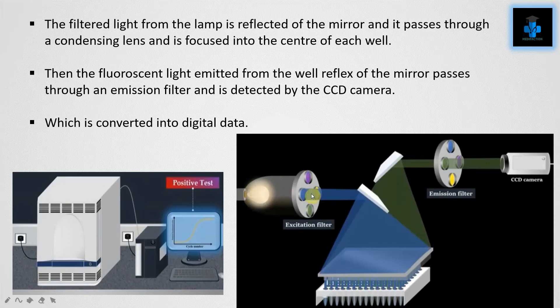A charge-coupled device, or CCD camera, is also used. The filtered light from the lamp is reflected off the mirror, passes through a condensing lens, and is focused into the center of each well. The fluorescent light emitted from the well then reflects off the mirrors, passes through an emission filter, and is detected by the CCD camera, which converts it into digital data.